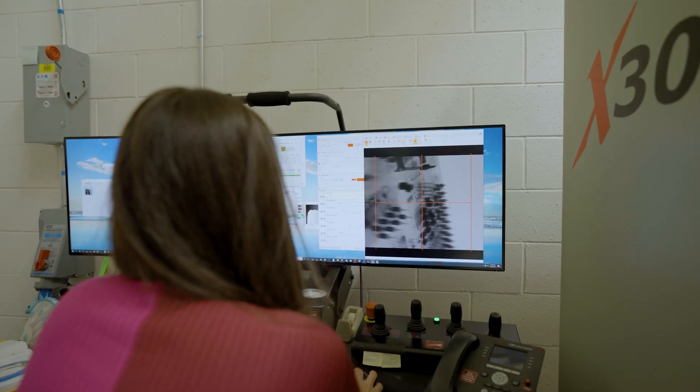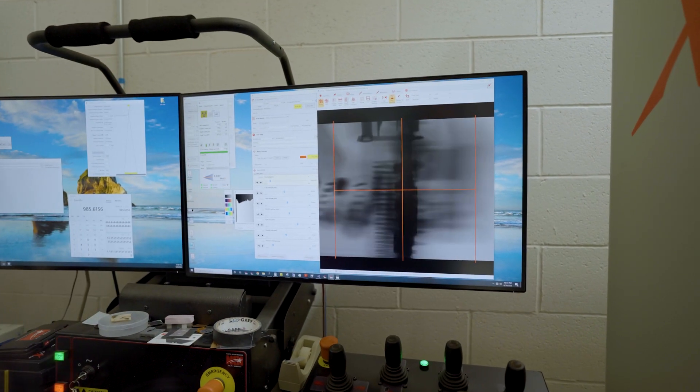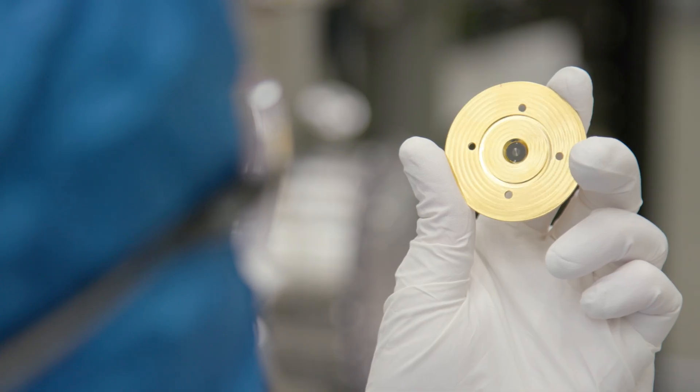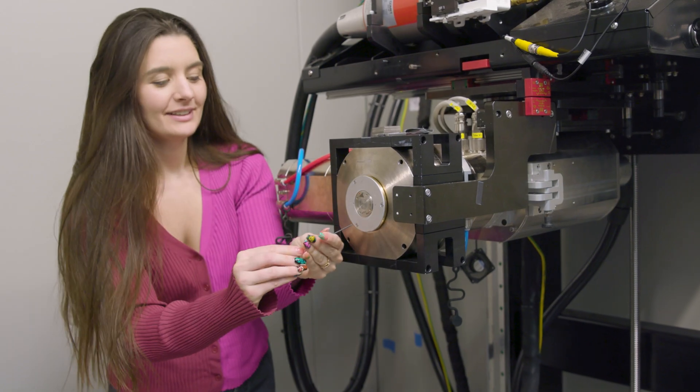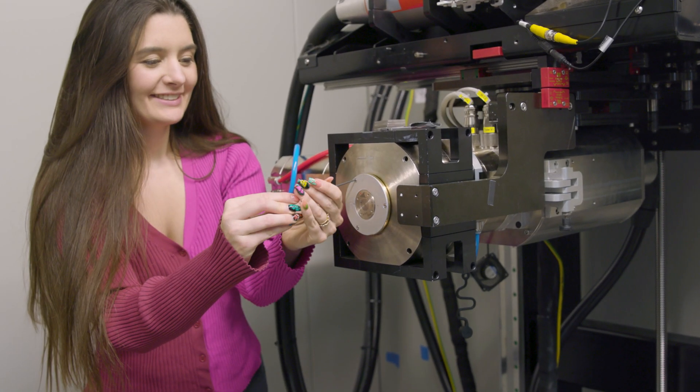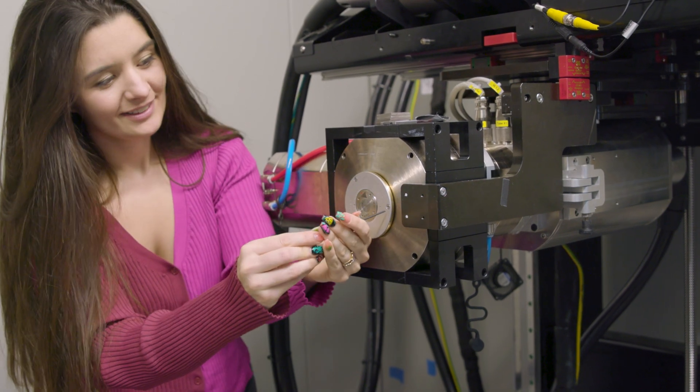We're taking microelectronics fabrication techniques and using really small scale nano or micro features of different metals all within the focal spot size of our x-ray tube, and that allows us to generate multiple different x-ray energies to use for interacting with the sample under test.